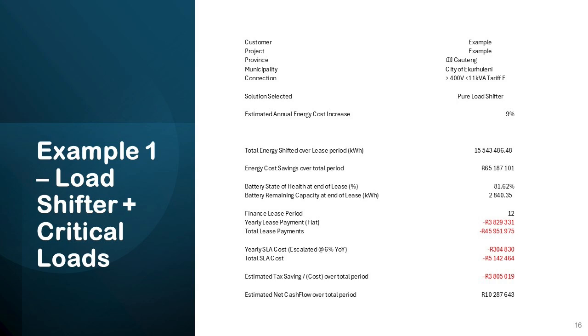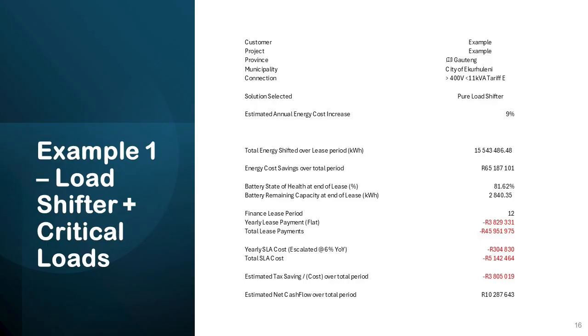And once we've run the model, we see that the total energy that is shifted over a 12-year period, which is about 6,000 cycles, is 15.5 gigawatt hours. This leads to a total saving of more than 65 million rand over that period. At the end of that period, the state of health of the battery has still got more than 80% left. And that's very important. We have a lot of competitors that promise end of life health conditions of 70 or even 60%. And we disagree with that. So we are very conservative in the way that we consider the system to be end of life, and that would be close to 80%. The remaining capacity of the battery is around about 2.8 megawatt hours in the specific case.